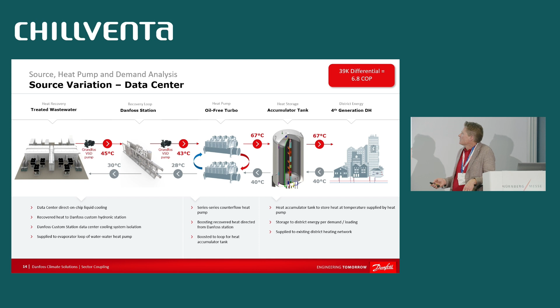This is our own data center. The other thing we point out is, if you want a soundbite, the only enemy of integrated energy system designs is DX systems, or direct expansion systems. If it's hydronic, then we know going into it—if it's hydronic on the heating side and hydronic on the cooling side—we know we can create a system that's going to have less than a 5-year payback, more likely less than a 3-year payback. If it's hydronic, it's relatively easy.